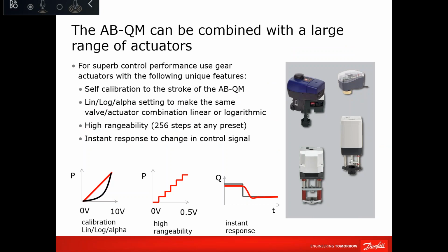Now, since we said it's a pressure independent control valve, you need the actuator. One thing to notice here: all these actuators are manufactured by Danfoss in the same factory where we manufacture the valve, which means the actuator is manufactured for the PICV. It's not like one actuator that will work on different valves. No, it's a specific actuator for that PICV. Why? As we were saying, we are changing the setting on these valves. We want the actuator to be able to recognize the setting we are doing on the valve. So the actuator has self-calibration to suit the setting percentage that you have put on the valve.